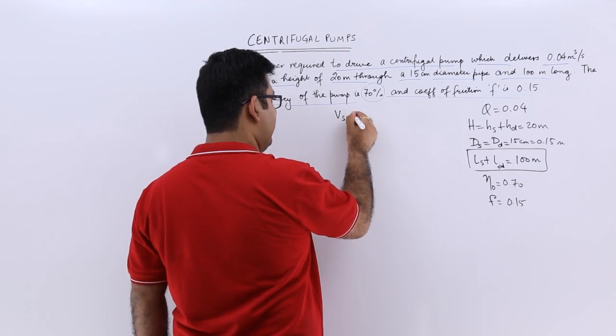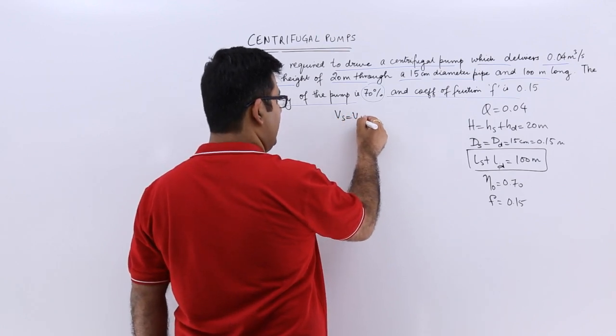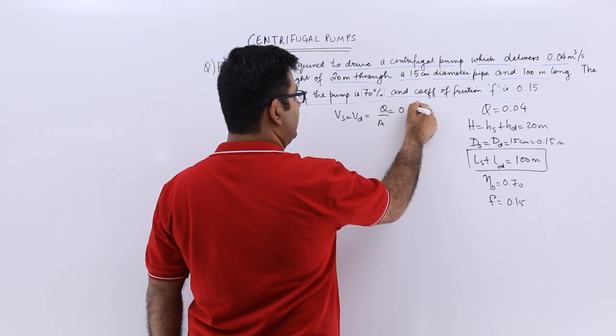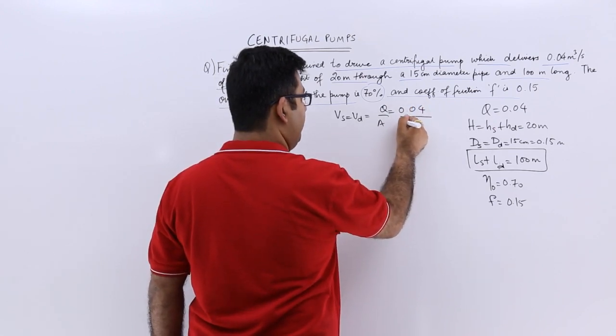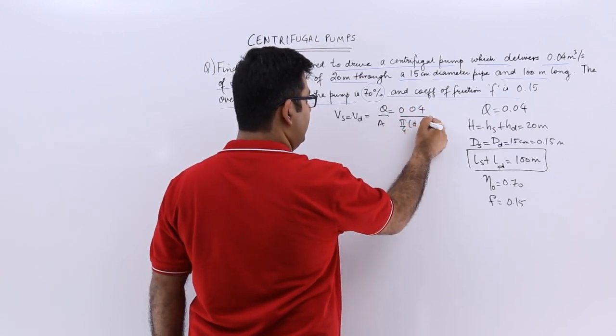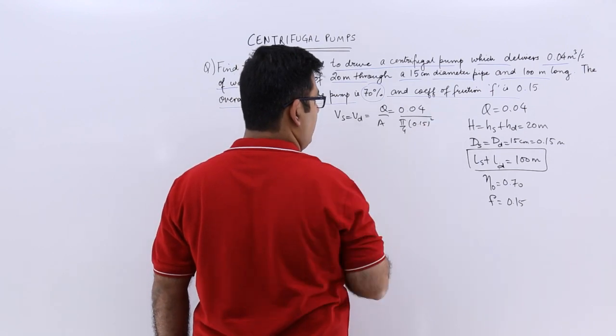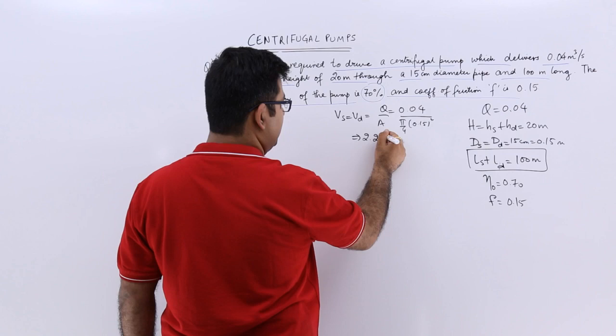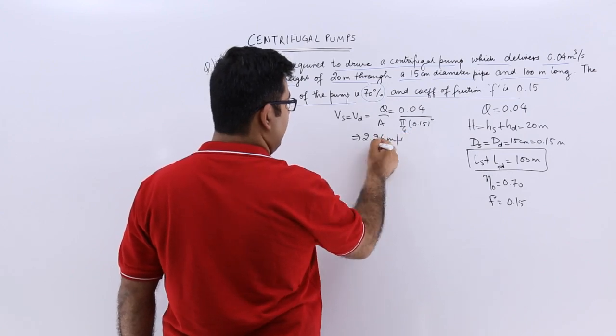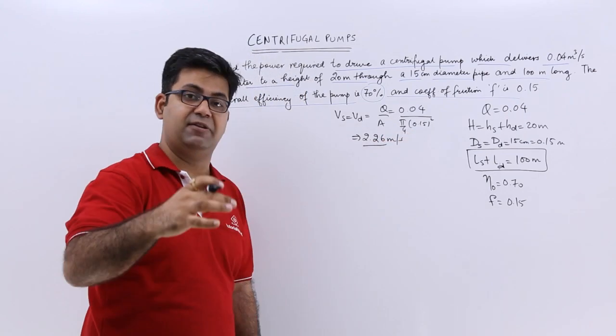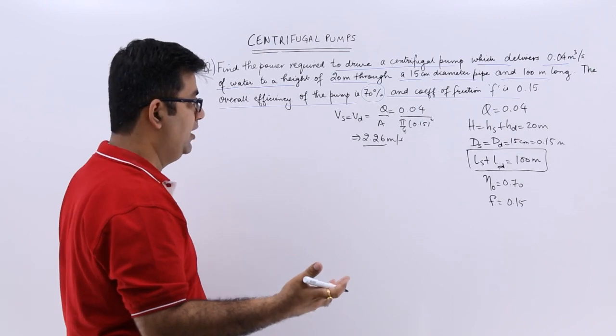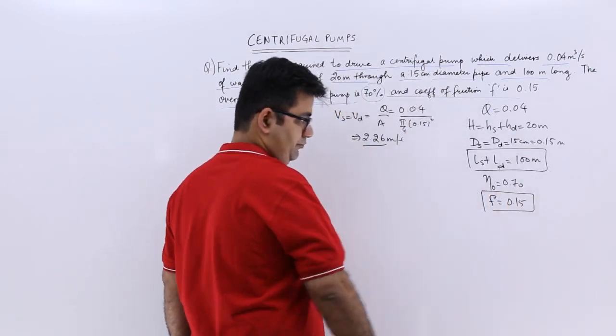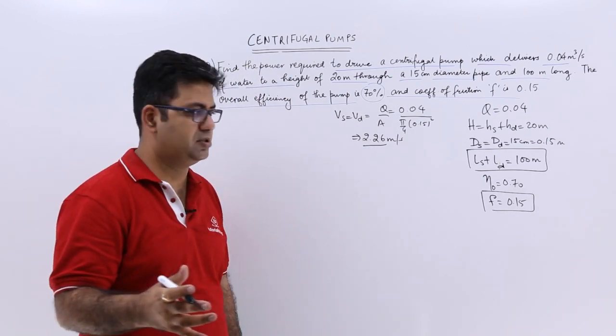Let's first find out the velocity. The velocity in the suction pipe equals the velocity in the discharge pipe: Q divided by area = 0.04 divided by (π/4 × 0.15²). This gives a velocity of 2.26 meters per second — that is the velocity in both the suction pipe and the discharge pipe. Now, since friction is present, let's calculate the total friction loss.